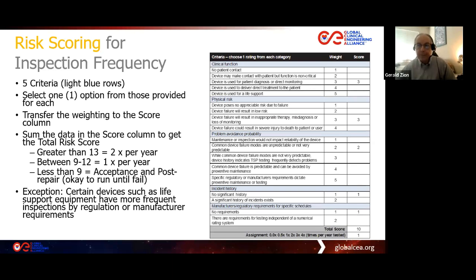If it is less than 9, we will for sure perform the acceptance or incoming inspection and post-repair, but these are low enough risks that they are actually okay to run until fail, and we will not add these to the periodic inspection or preventive maintenance schedule. We will just run them till they fail, and then we will do the repair at that point because they're low risk. These are the exam lights and exam tables as an example.